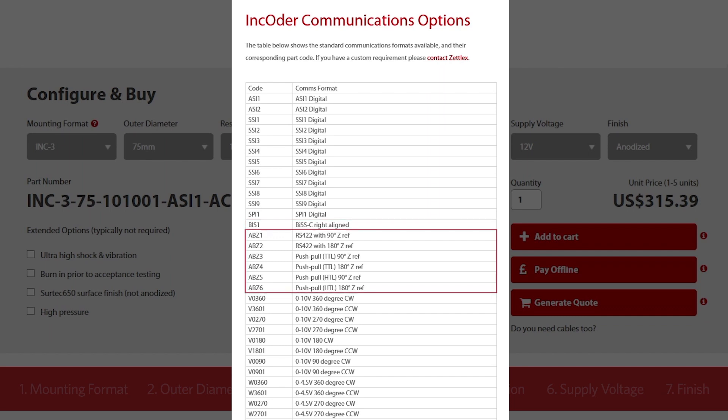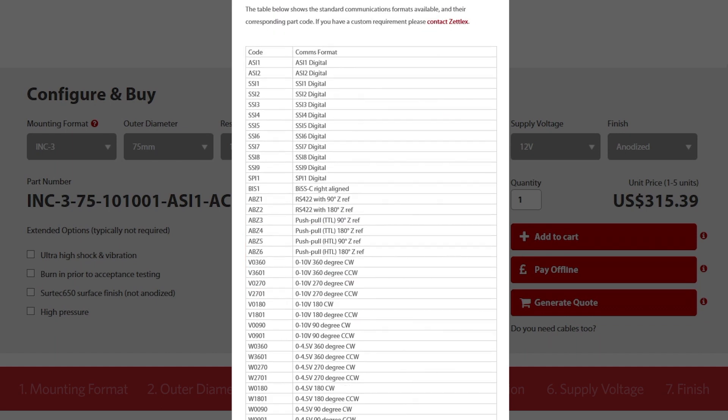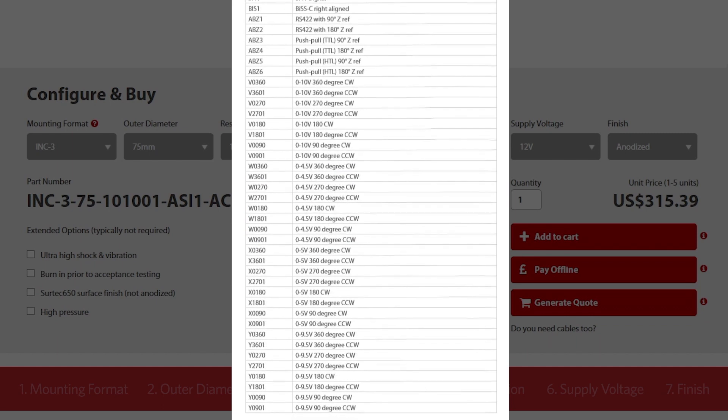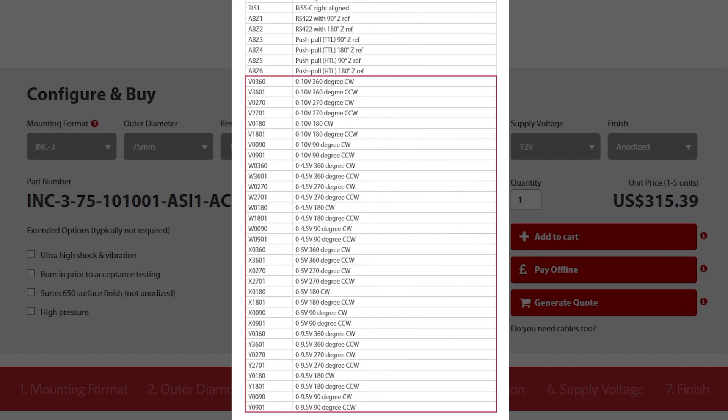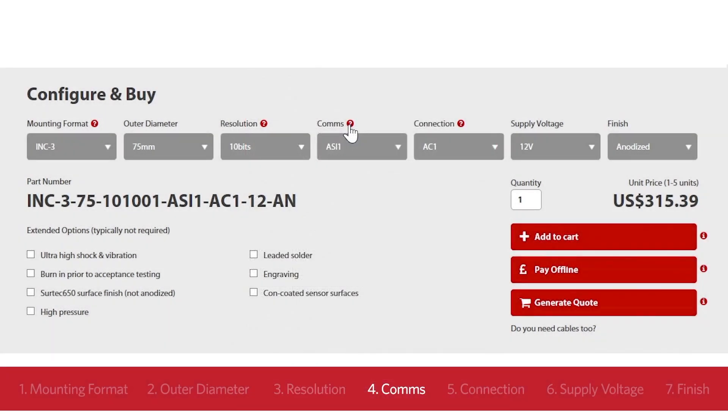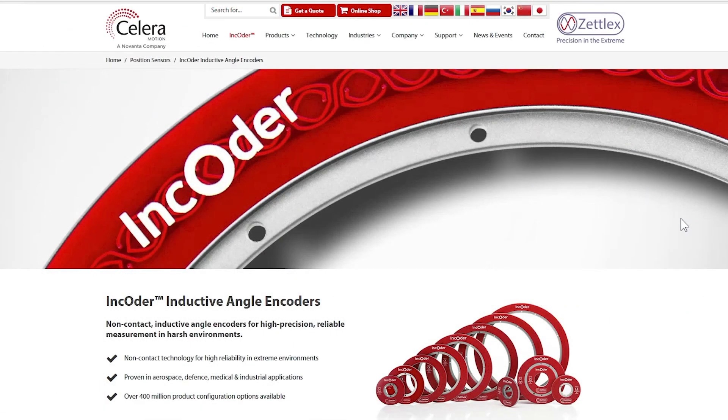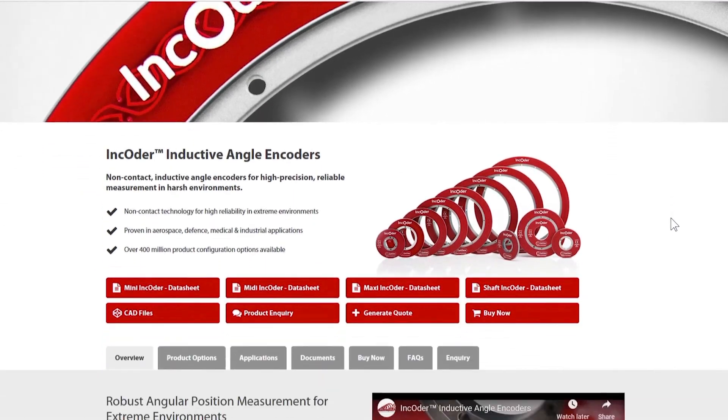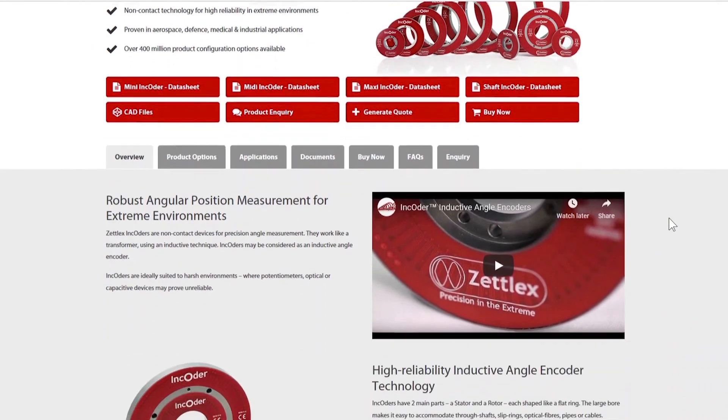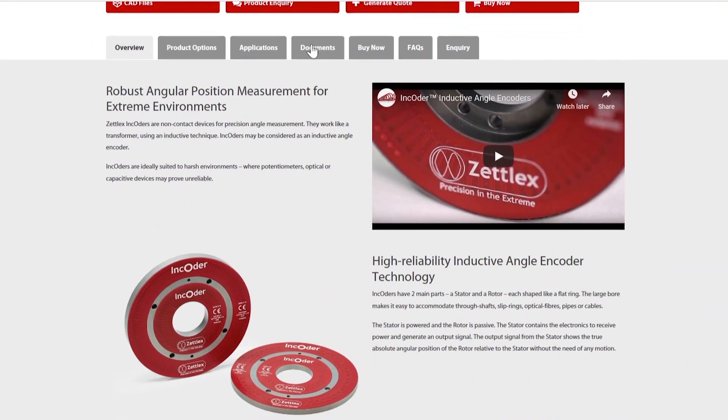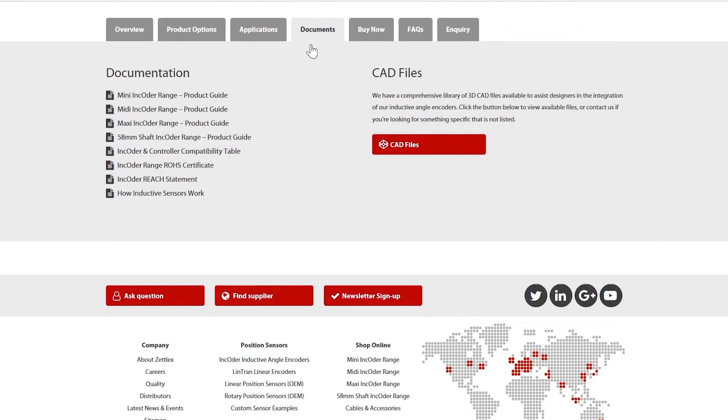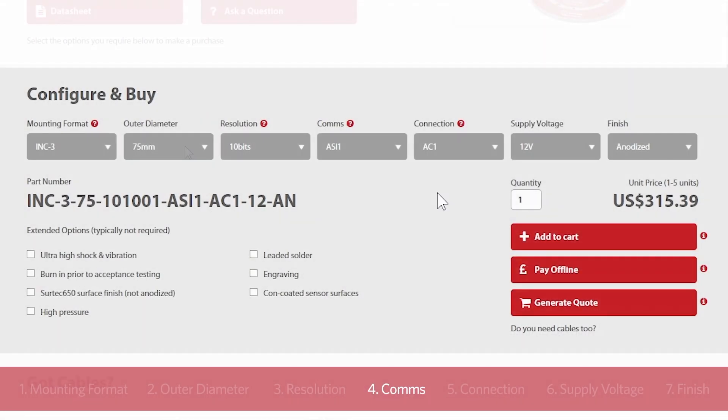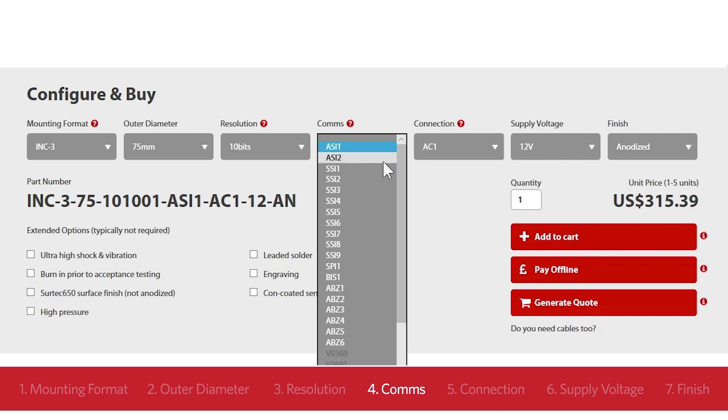AB pulses is mostly used for incremental encoders and motor drives. The analog voltage outputs of 0 to 5 or 0 to 10 volts are mainly used as replacements for potentiometers, usually in process control, test and development applications. If you're looking to match an encoder within a controller, you can check compatibility with the tables shown on the Zettlex website. You'll find these in the document section on the encoder part of the website. In this example, we'll go for the most frequent choice, ASI1.